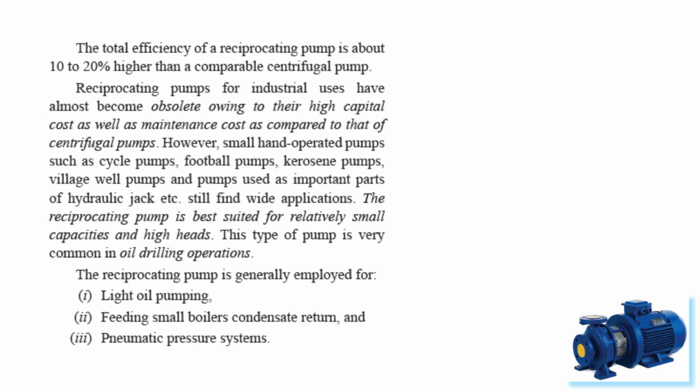The total efficiency of a reciprocating pump is generally 10 to 20 percent higher than that of a centrifugal pump, but we have a disadvantage due to their high capital cost, and as many moving parts are there, we have to spend on maintenance cost. However, small hand operated pumps like cycle pumps, football pumps and kerosene pumps in villages still use the reciprocating pump.